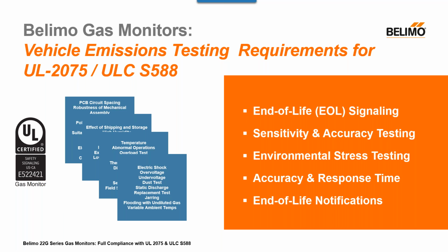Another is sensitivity and accuracy testing. The UL 2075 mandates rigorous testing to confirm that detectors can accurately measure gas concentrations, even at very low levels. This is crucial for preventing exposure to gases that can have severe impacts on health over time.